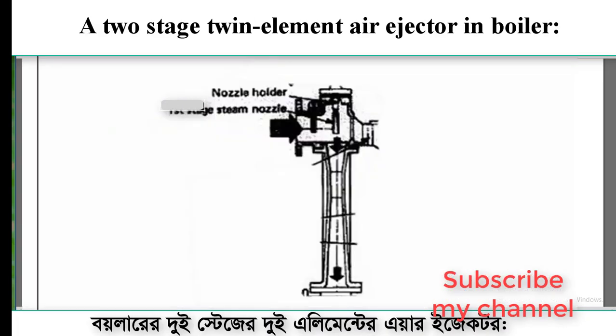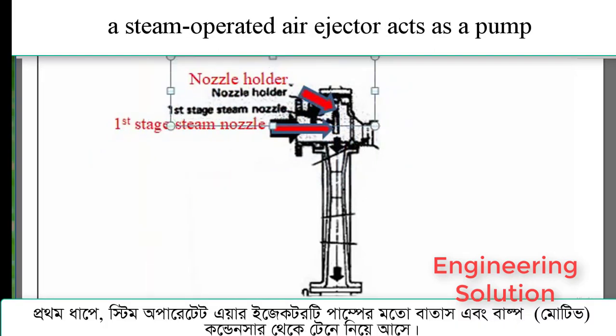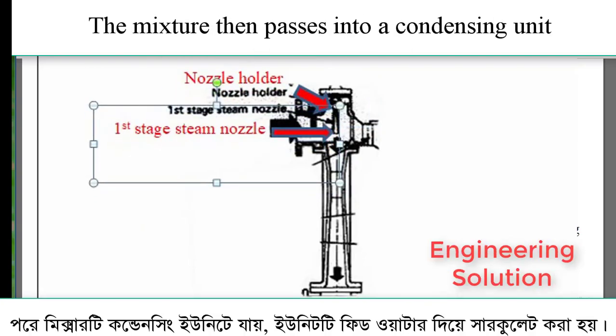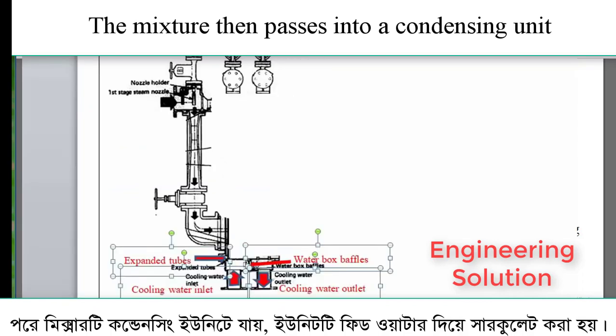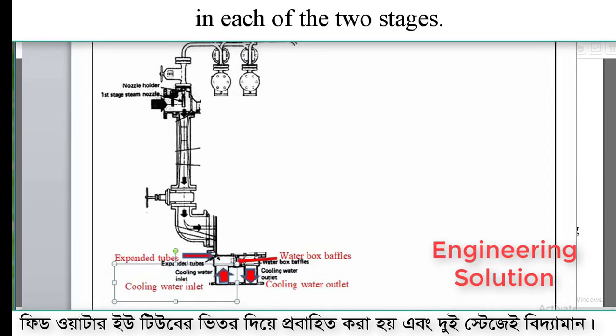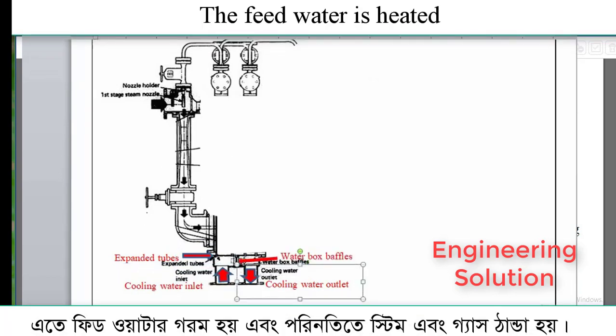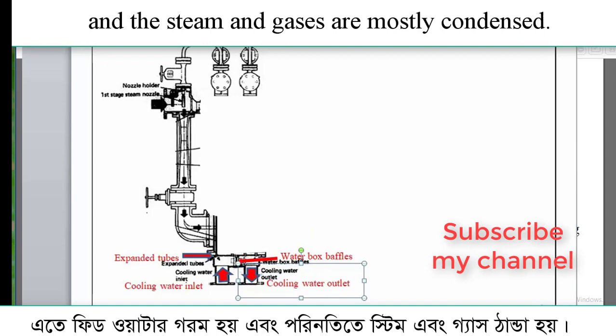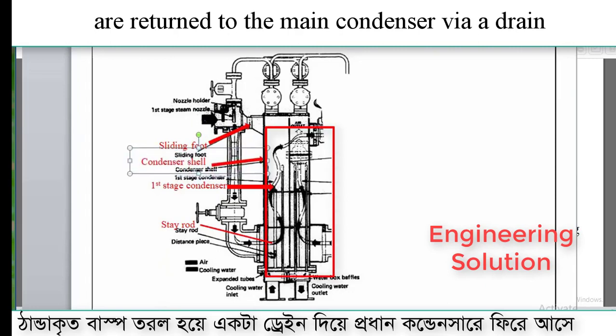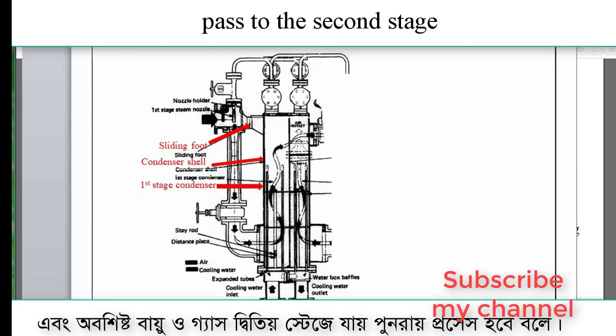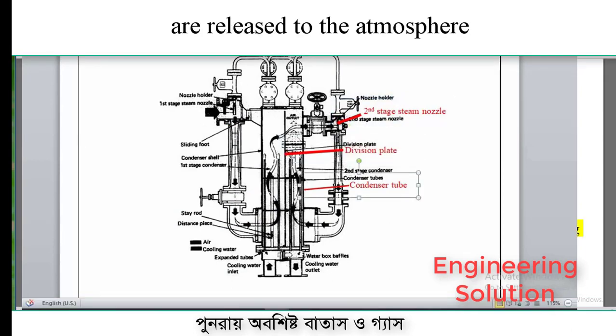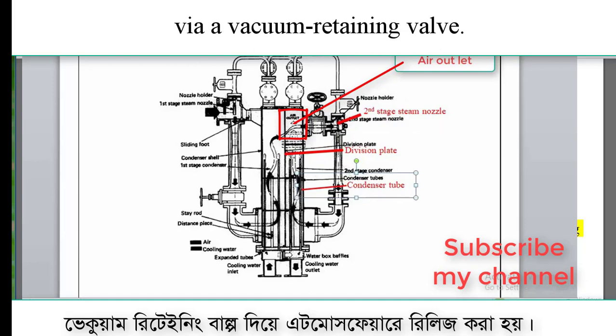A two-stage twin element air ejector in a boiler: in the first stage, a steam-operated air ejector acts as a pump to draw the air and vapors from the condenser. The mixture then passes into a condensing unit which is circulated by feed water through U-tubes in each of the two stages. The feed water is heated and the steam and gases are mostly condensed. The condensed vapors and steam are returned to the main condenser via a drain, and the remaining air and gases pass to the second stage where the process is repeated. Any remaining air and gases are released to the atmosphere via a vacuum retaining valve.